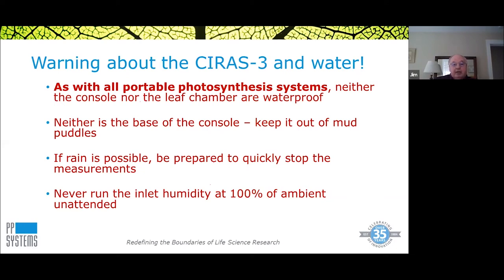If you run into condensation inside the leaf cuvette, that takes a long time to dry out and correct itself. So you're essentially done for the day if that happens. It takes a long time to get everything dried out again and up and running again. So the warning there is just never run it at 100% of ambient unless you're going to be right there. So those are some warnings.